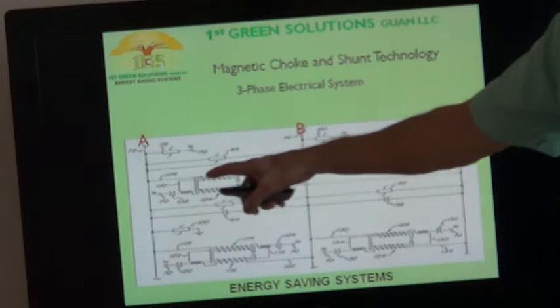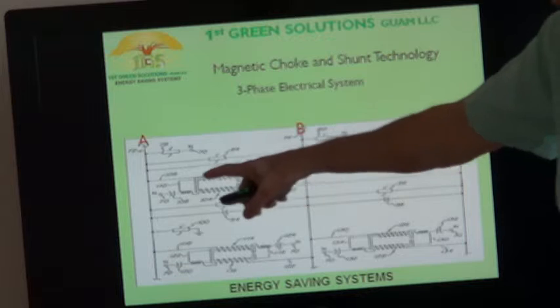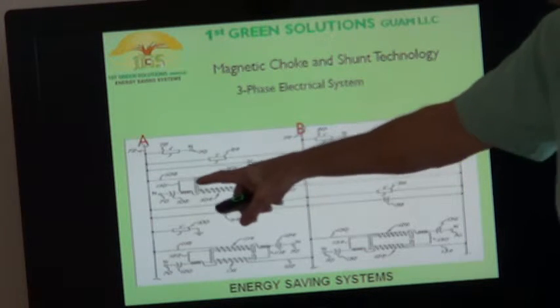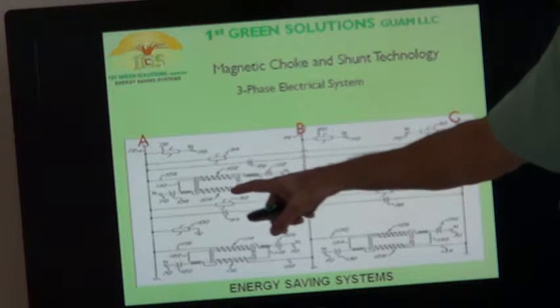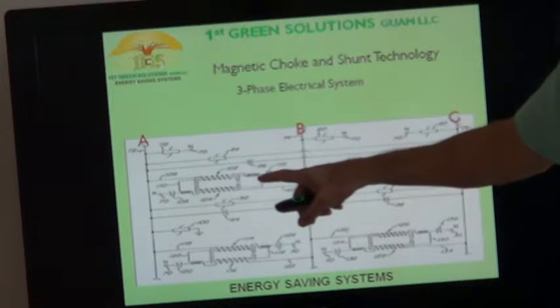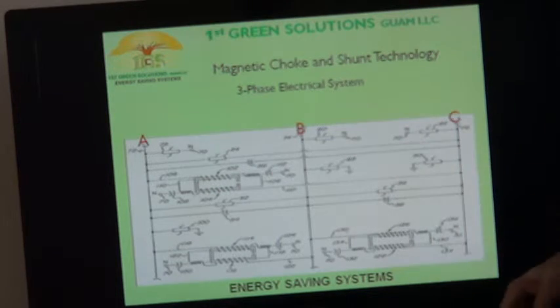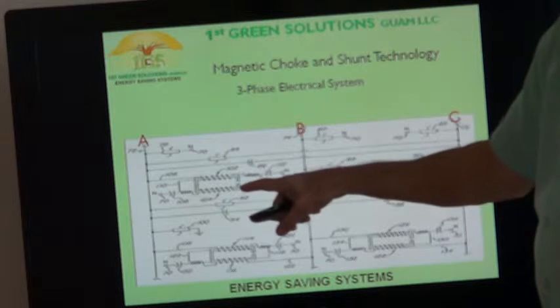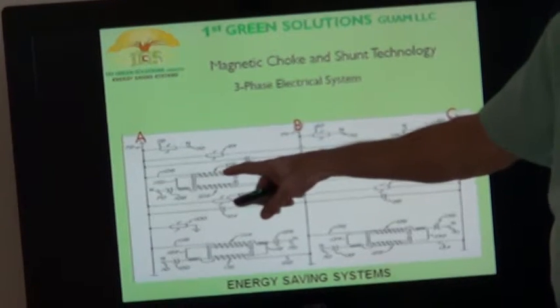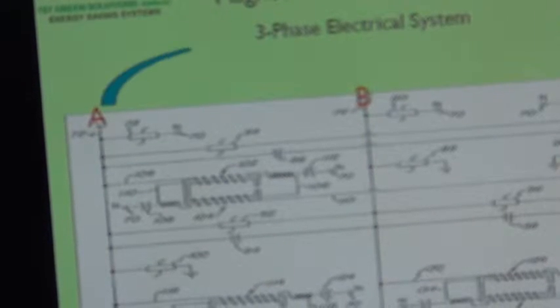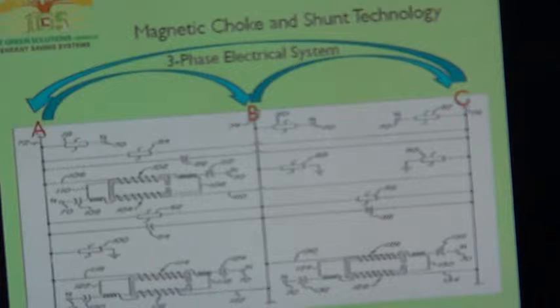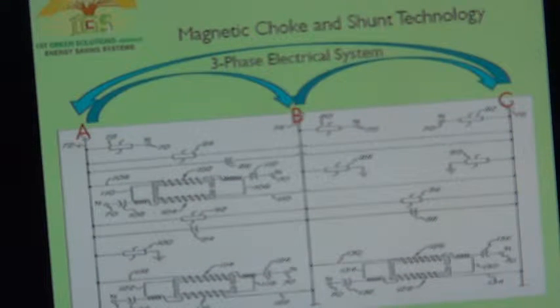This technology here takes the energy and wraps it around this, from this phase, wrapping it around this coil. This is a solid iron core within the USIS technology. It is then wrapped outside of the core and passed back underneath the core of the adjacent phase. By doing this, this energy is being picked up, captured with the chokes, and then reinserted into the adjacent phase. So when we complete the installation, A phase energy is captured and shunted back into B. B is captured, shunted into C, and C is captured and shunted back into A. This allows us to also balance your imbalanced loads on your amperage.